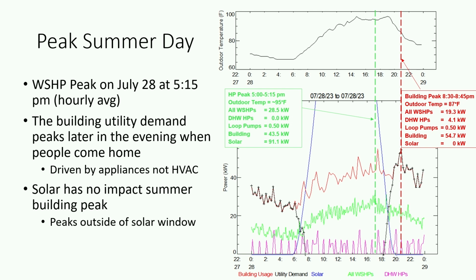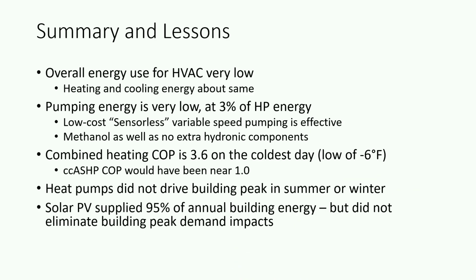So I think the interesting thing about this is that the peak demand for this building was not driven by the HVAC system. It was driven by appliances in the apartments and what the people were doing. So the overall summary: heating and cooling energy use in this building was very low, and energy use for heating and cooling were about the same. Pumping energy for this building was extraordinarily low for the reason we talked about. The low-cost Sensorless variable speed pumping is very effective, with no extra components in the system. Combined COP was still 3.6 on the coldest day, even when it was -6.